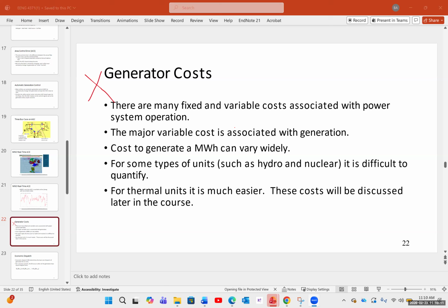So let me give you an example. For a 1 GW system for gas, it's going to be $200-300 million, and it takes roughly 1 to 2 years. But if you want to build the same nuclear power plant, it costs $5-6 billion, and sometimes even more. And at least it takes a decade. But with gas, you don't know what the price of gas is going to be, but with nuclear, you have a better idea.